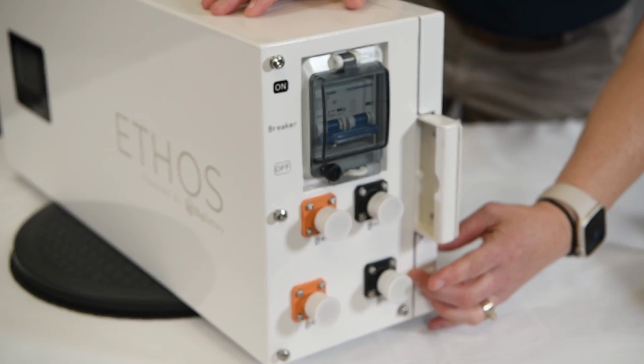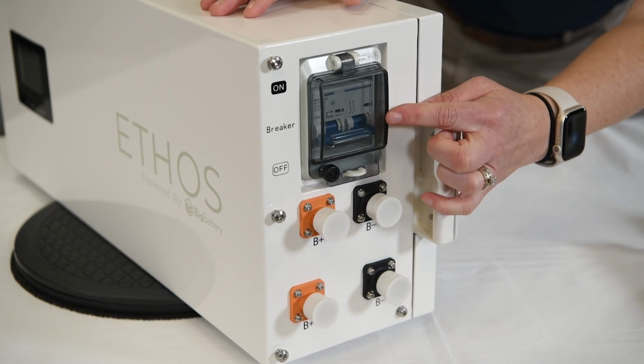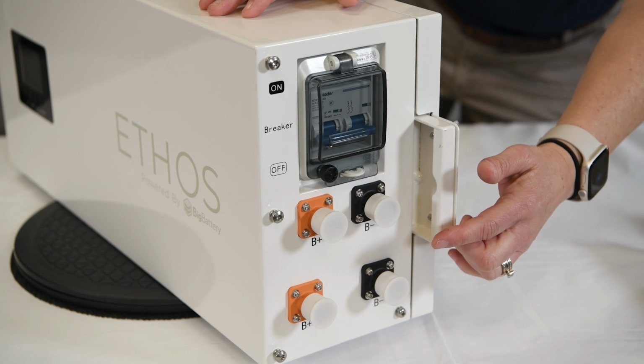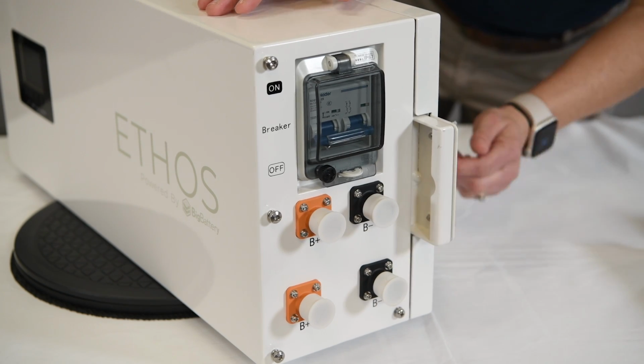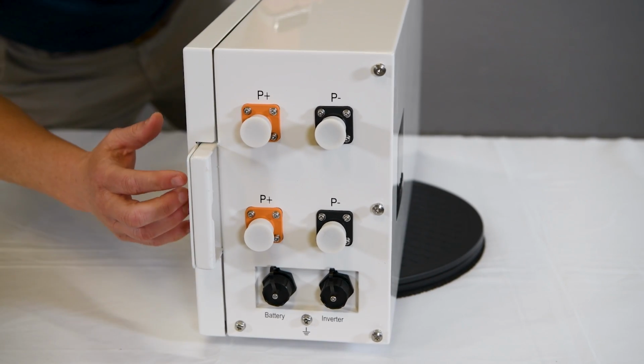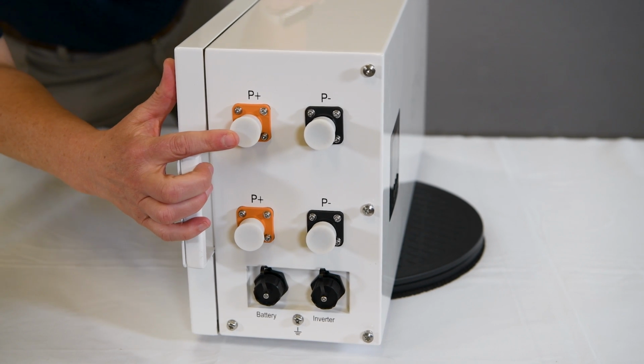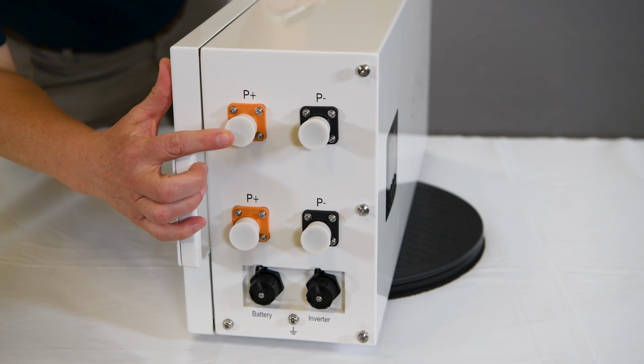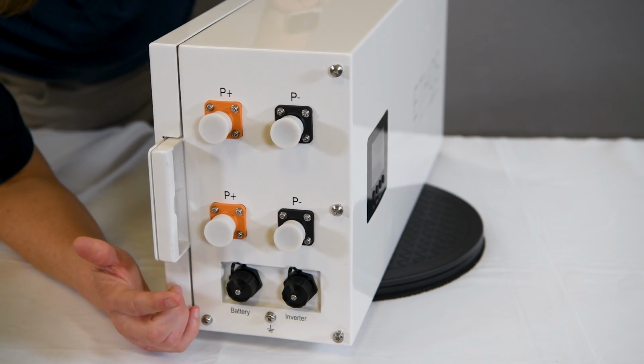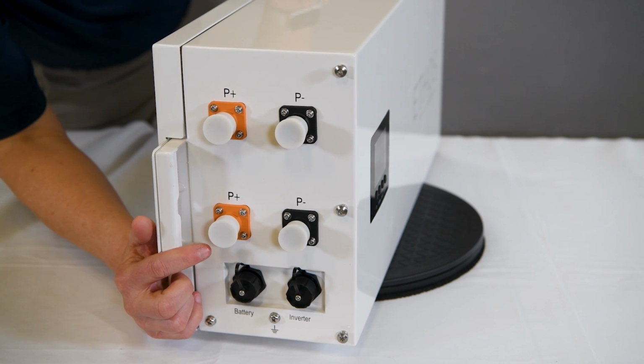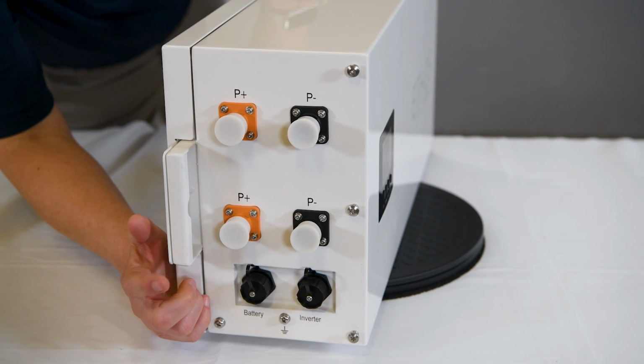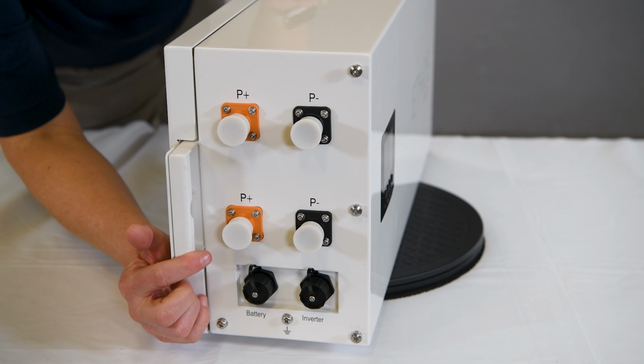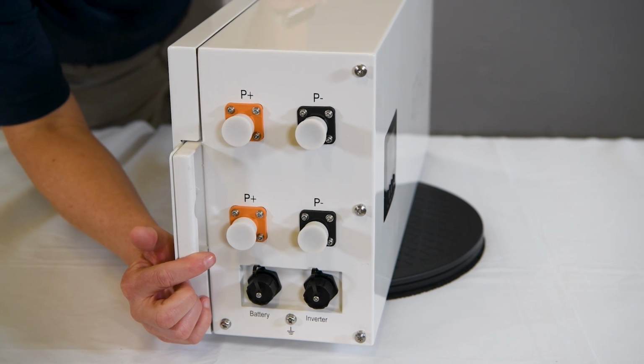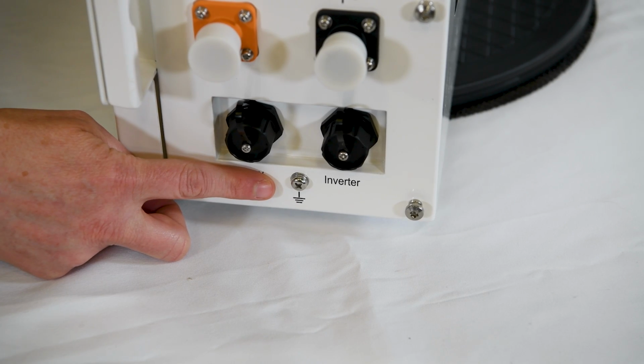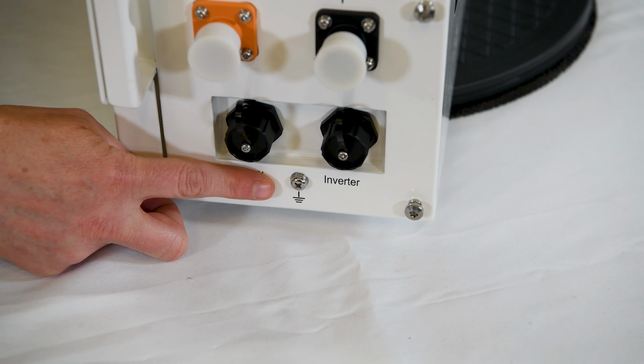On the right side, we see our battery terminals and our battery breaker, which we'll talk more about later when we begin our installation process. On the left side, you'll find our power ports designed for seamless connection to the inverter alongside our communication ports that facilitate closed-loop communications, ensuring synchronized operation between the batteries and inverter. Additionally, there's a grounding screw provided for enhanced system safety.